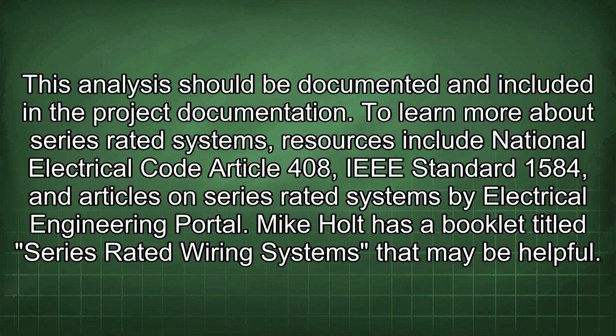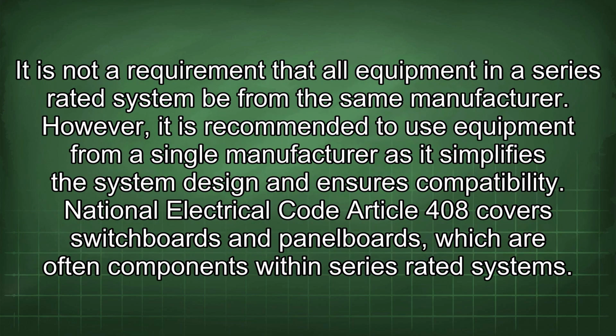To learn more about series-rated systems, resources include National Electrical Code Article 408, IEEE Standard 1584, and articles on series-rated systems by Electrical Engineering Portal. Mike Holt has a booklet titled Series-Rated Wiring Systems that may be helpful. It is not a requirement that all equipment in a series-rated system be from the same manufacturer. However, it is recommended to use equipment from a single manufacturer as it simplifies the system design and ensures compatibility.